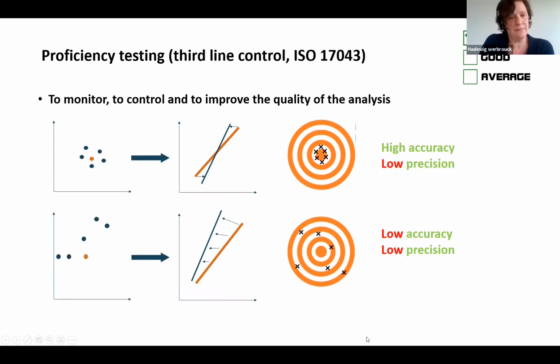A third possibility is a high accuracy and a low precision. In this situation, the repetitions are not so close to each other, but the average is close to the reference value. When different concentrations are analyzed, you see a tilt in the regression, a positive deviation, for example, in the low fat range, and a negative deviation in the high fat range, and the mean is okay. A fourth possibility is a low accuracy and a low precision. In this case, you see a shift and a tilt of the regression.